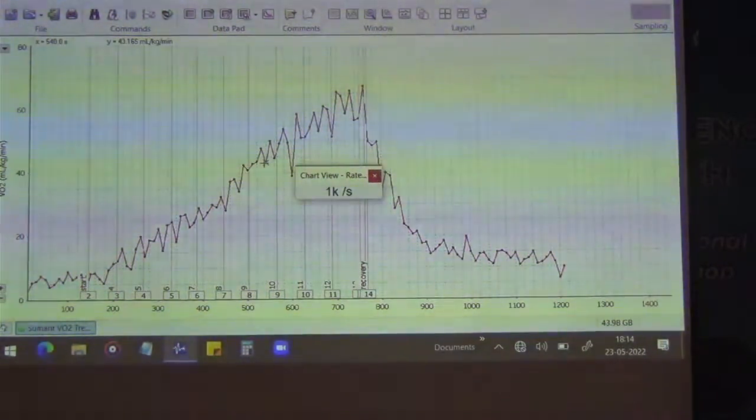Ideally 16.5 O2 and around 5 carbon dioxide, balanced with nitrogen. The idea is to make this known: this is a known cylinder volume and value. You have to standardize your equipment with respect to this cylinder. That is part of gas calibration.